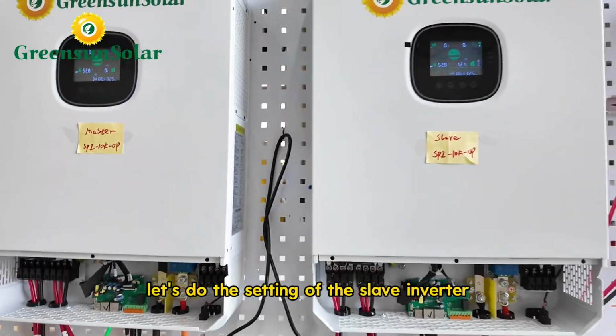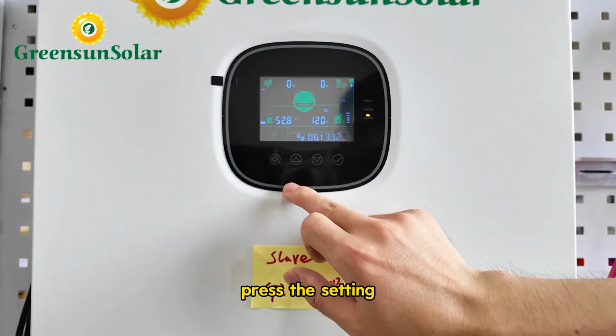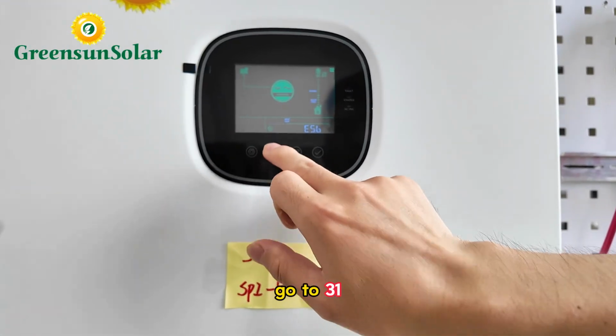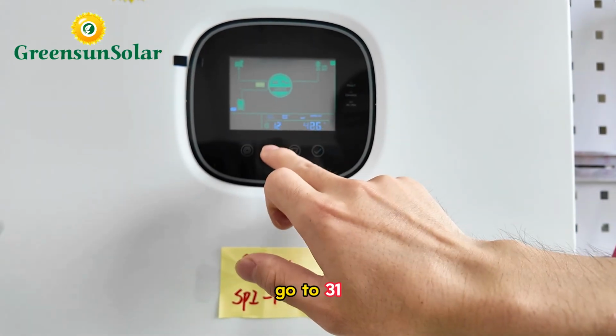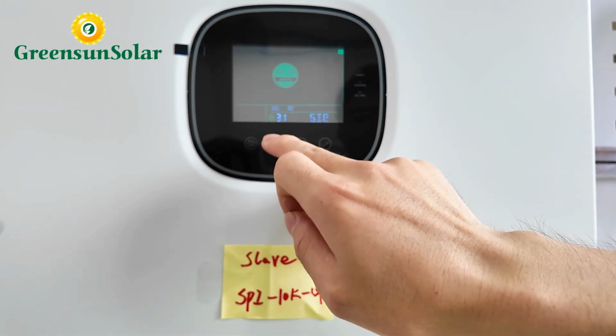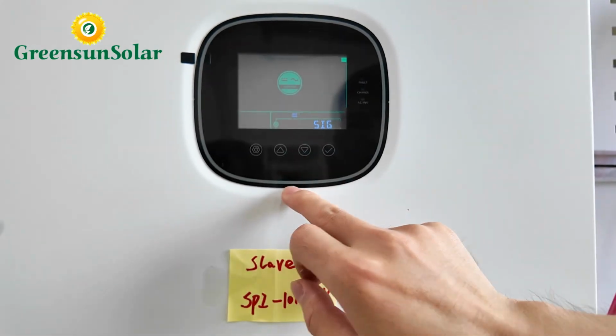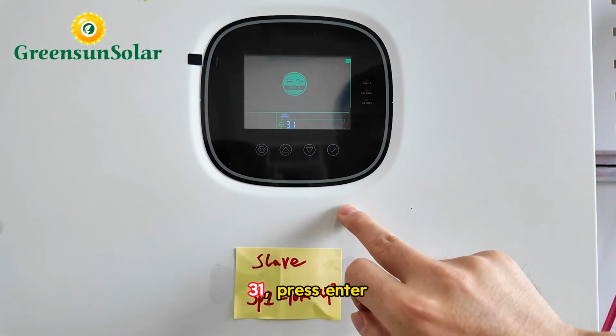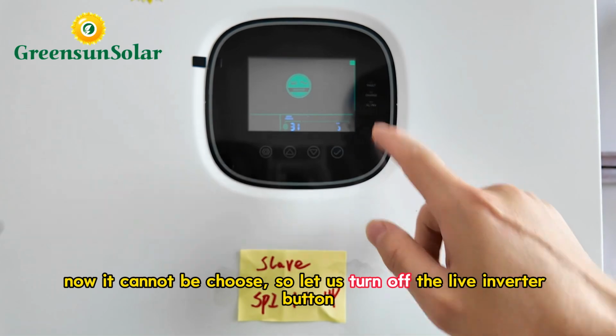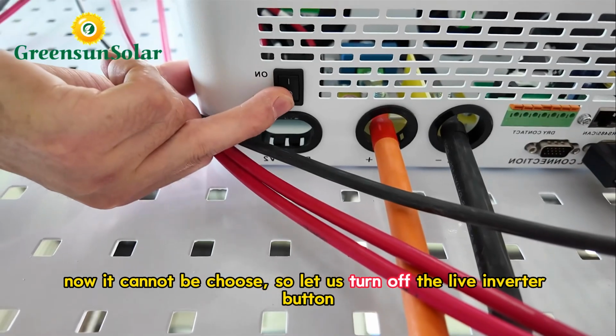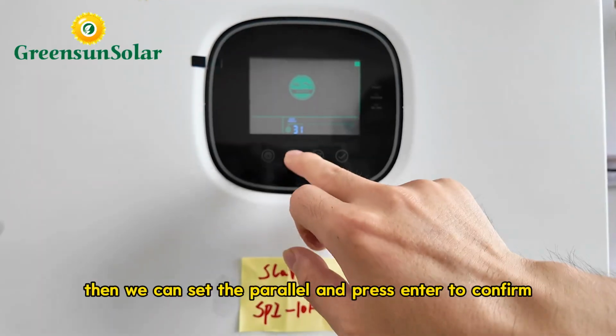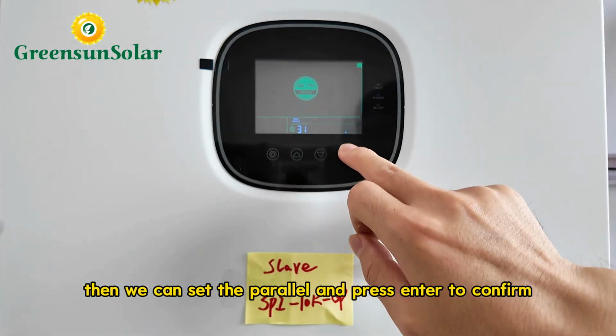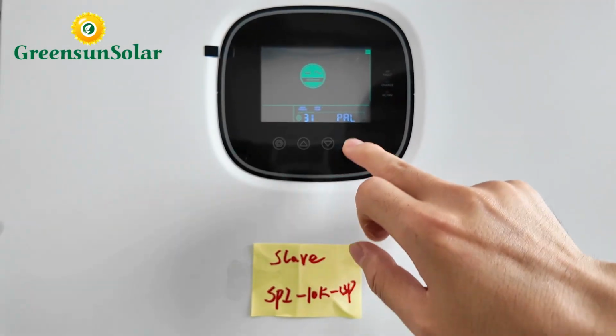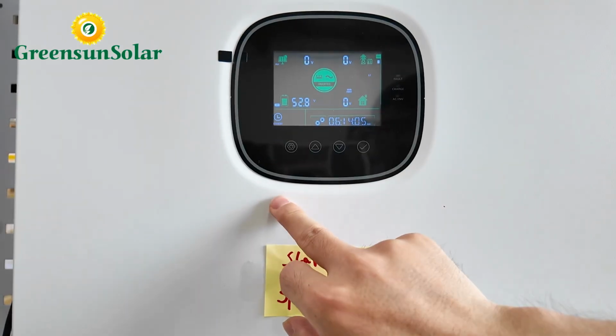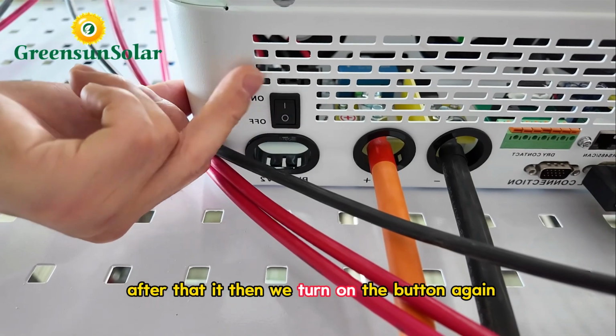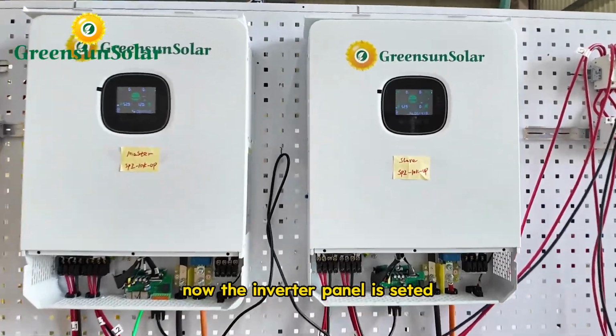Let's do the setting of the slave inverter. Press setting. Go to 31. Press enter. Now it cannot be chosen, so let us turn off the slave inverter button. Then we can set it to parallel and press enter to confirm. Okay, then after that, we turn on the button again. Okay, now the inverter parallel is set.